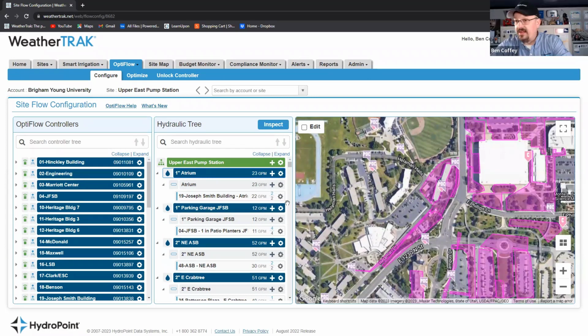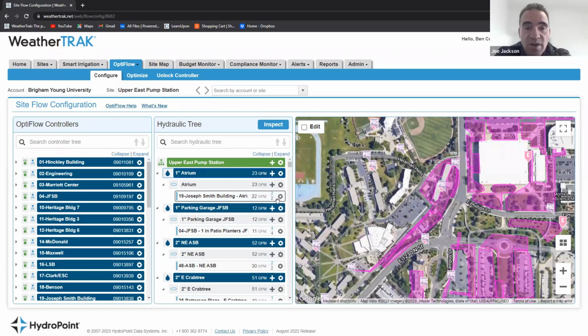So here we see that there are 2 stations on this section of the system we're talking about, with the largest flow rate being 22 gallons a minute. That works because the flow rate for the atrium was set at 23. So we know we have enough water to run the largest station on that.